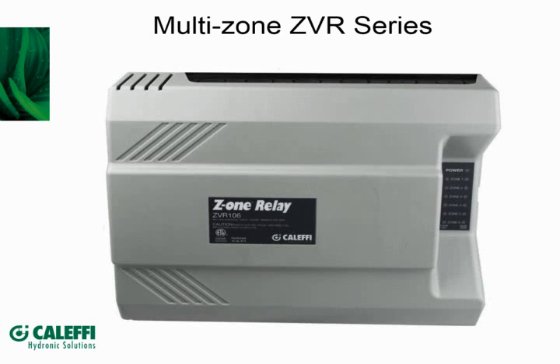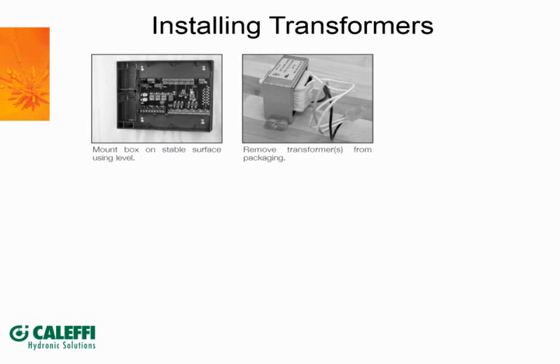So that gets us into the Zone Relay box. The Zone Relay box is a little bit more complex because you're interfacing the zone relays and the pumps. So what we've done here is we have 1 or 2, depending on what model you have, heavy 40 VA transformers in there. The first thing we noticed when we got it produced was that the one side is awfully heavy to maneuver and to mount and for shipping reasons. So we created a new box where the transformers nest separately inside the cardboard shipping box.